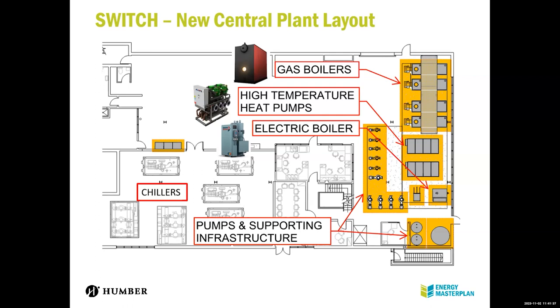The electric boilers would run off peak, so that's mostly overnight when our electricity rates are low. And then the heat pumps would run whenever we have simultaneous heating and cooling happening. So with this configuration, we're expecting to reduce the on-site natural gas use on the campus by 70%, which is quite remarkable.